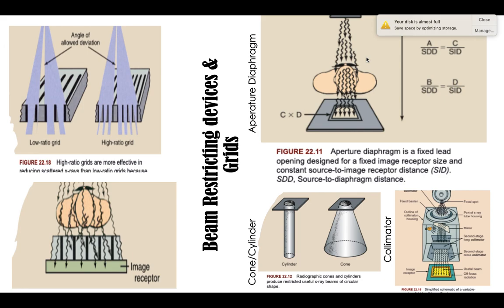A variable aperture collimator, which is most commonly used in radiography, uses a small lamp and a mirror placed by the X-ray beam to aid the technologist in positioning and lining up the anatomical structure. It decreases the field size, and that helps to minimize scatter radiation.